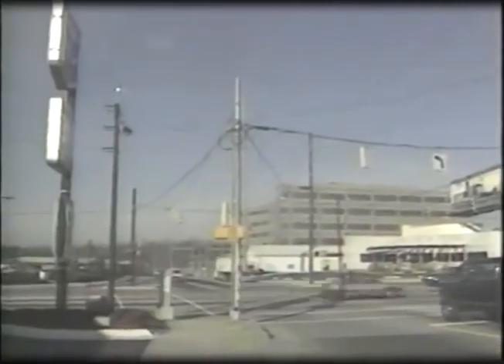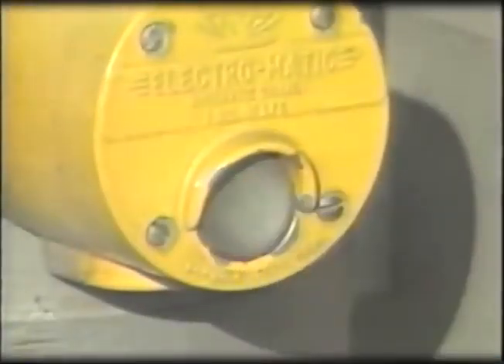All of these electromagnetic threats can enter the controllers along several paths. The most common path is the power line, followed by communication cable. Other paths are support cables, pole grounds, vehicle detector loops, signal leads, and any other cables entering the cabinet, like a pedestrian push button. Openings in the controller cabinet, like door seams and vents, can also provide a path for electromagnetic energy to enter the cabinet. When a threat enters the cabinet, it can upset circuits or destroy components. This illustration shows that the transients produced by these threats can easily exceed the tolerance levels of circuit components.